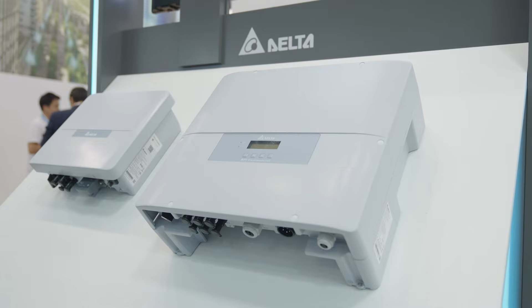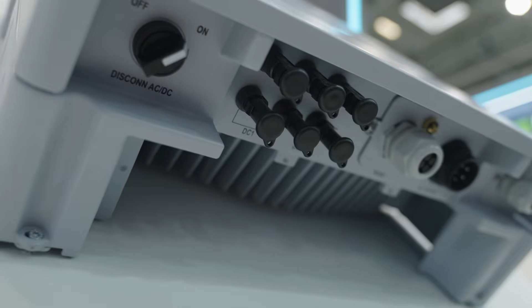Coming to our 3-phase inverters, also for residential applications, we have our product family starting from 6, over 8, up to 10 kilowatt. You can see we still have an LED display on it, which makes the life of installers much easier because they can do the settings and commissioning right in front of the inverter. We have a fanless design, which keeps the noise level low, and a multiple MPP tracker design with 2 MPP trackers in total.